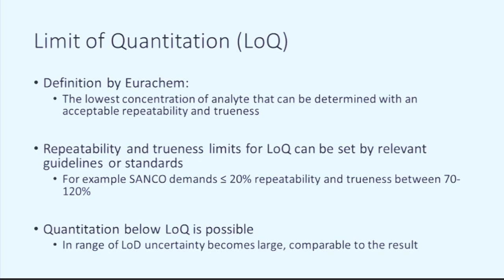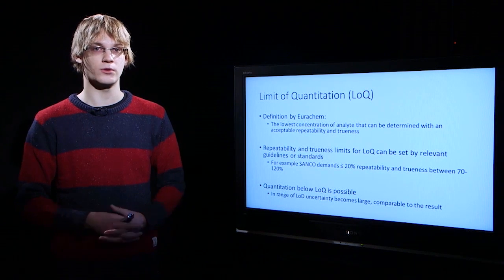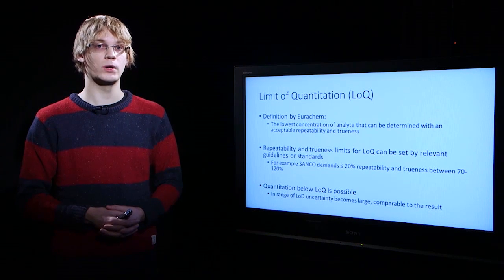It must be noted that quantitation below LOQ is still possible and this limit has therefore been set somewhat artificially. However, below LOQ the relative uncertainty can become very large, and in fact in the range of LOD the uncertainty value can become even comparable to the result itself. In the following videos we will discuss further the use of LOQ and how to estimate this value.